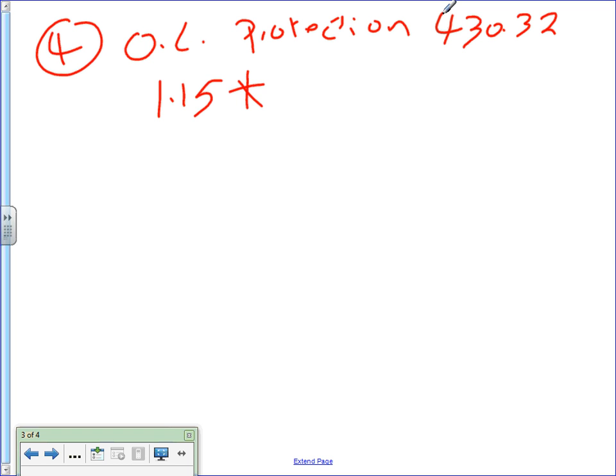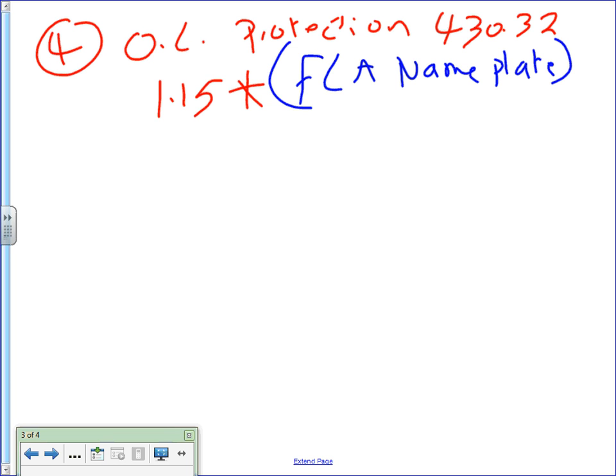The only place where you have to use the nameplate. So I have to give you the full load amp nameplate. Not the full load current, the full load amp nameplate. Okay, so given, this has to be given. You can't find it from a table. So do you guys remember what was the full load current that we got? 17, right? Typically, the full load amps on the nameplate is slightly lower than what you get from the table, okay? So I'm going to go there and I'm going to take 1.15 multiplied by 15 amps.